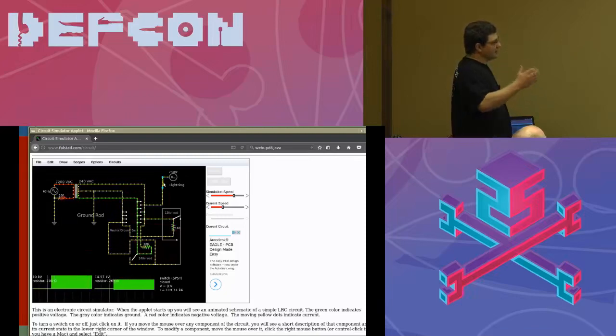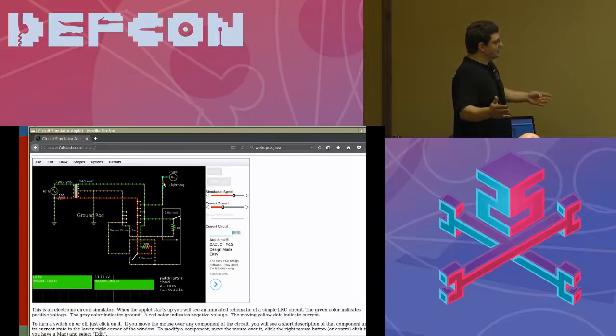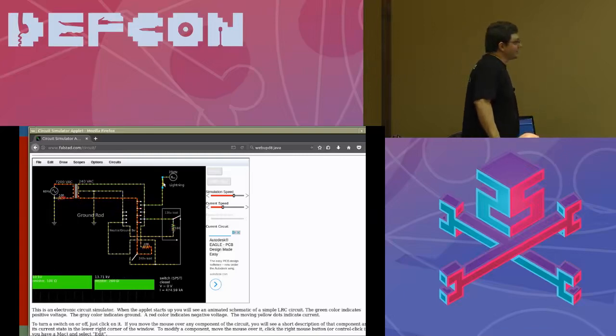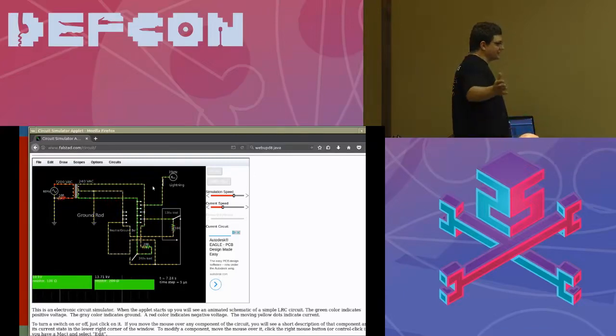We've got an external static charge that is in relation to ground. It's not self-contained within your house's transformer. The lightning or any static buildup in your house does filter out through the ground rod. It gives a potential reference to keep the ground near your house at the same reference voltage as the 0 volts we defined as the center of the transformer. But it really does not do much most of the time, other than exist to make sure your house doesn't float in relation to ground, and to shunt off any lightning or static charges.